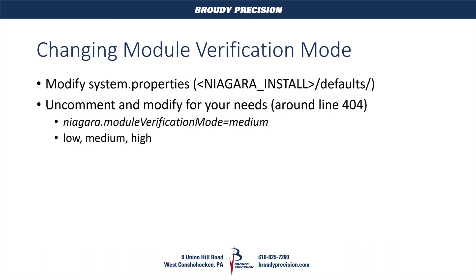To change the verification mode, go into your Niagara install directory in the defaults folder. There's a system.properties file, and inside that file there's a line called niagara.moduleverificationmode. By default it's commented out and takes the default built into the code — which is medium — but you can change it to low, medium, or high. That line is going to be around line 404, towards the bottom of the text file. We're going to take a look at that now, along with what modules not opening looks like and what the error messages look like in Niagara.